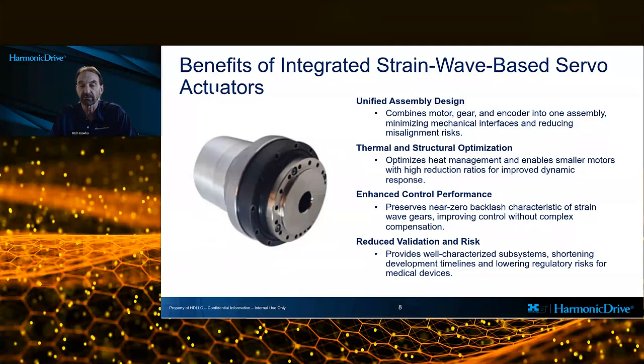For medical device manufacturers, integrated actuators can also reduce validation effort by providing a well-characterized subsystem with known life and performance data. This can shorten development timelines and reduce regulatory risk. Overall, integrated strain wave-based servo actuators shift complexity from the system integrator to the component level, where it can be more effectively engineered and controlled, resulting in higher reliability and more predictable performance in demanding medical applications.